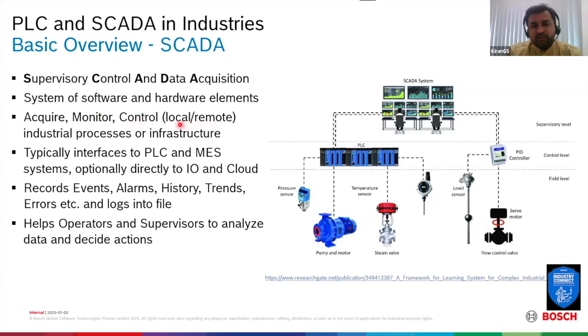This control can be even local and remote system. A simple SCADA system is visualized over here, but in practical terms it can be as simple as this, or as complicated as multiple PLCs and multiple PID controllers interconnected between every area of your manufacturing environment. So you can visualize this field level control, not from just one PLC or one PID, but maybe hundreds of PLCs and PIDs interconnected to a network system and then going to a SCADA.